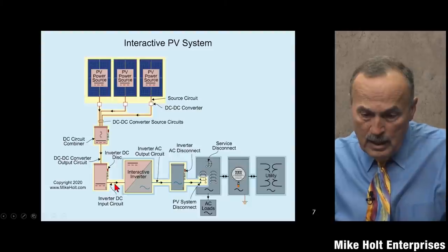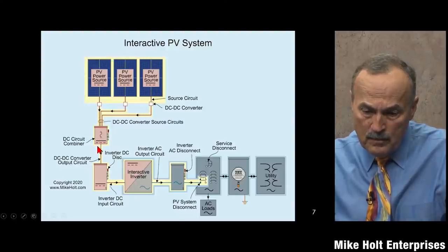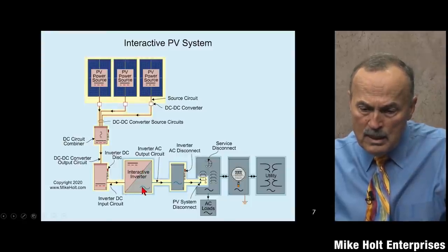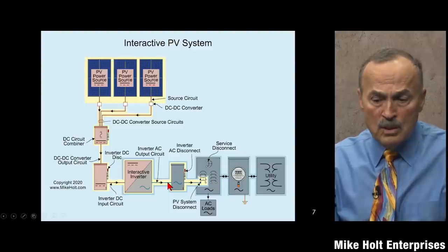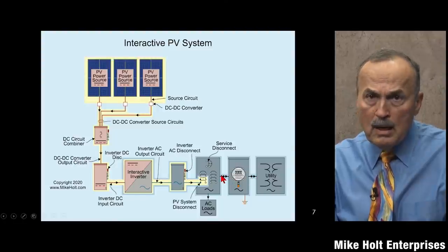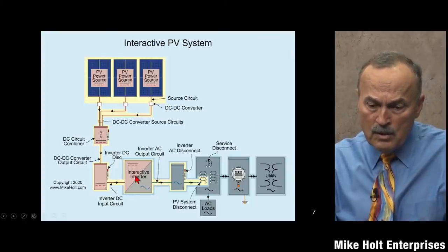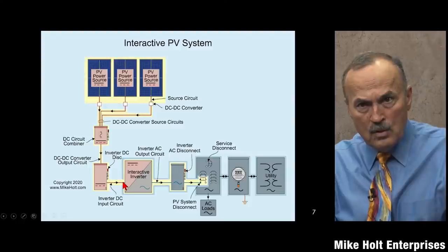Looking at this graphic again: here's the inverter DC disconnect, here's the inverter. The arrow going one direction shows DC coming in - we use pink and red lines to represent DC. Then we invert it to alternating current, shown in blue. The utility wiring is shown in black. The direct current coming into the inverter is called the inverter DC input circuit.